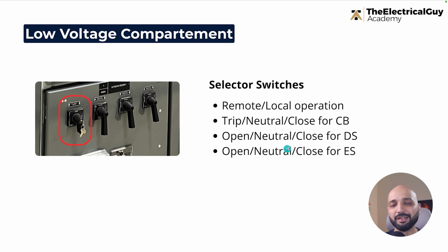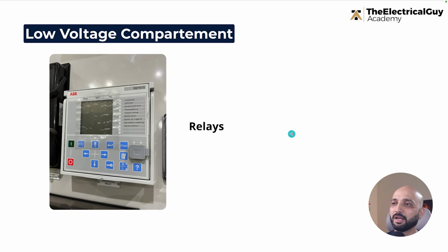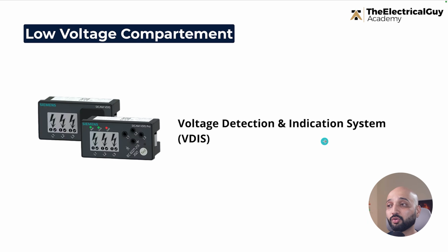And then of course, definitely relays. You will find a lot of relays placed there depending on the application. Different types of relays, electronic relays, and everything will be there. For example, you can see one relay here. It provides multiple functions. We have overcurrent, earth fault, sensitive earth fault, phase unbalance, thermal overload, breaker failure, condition monitoring, trip circuit failure. It's a long list, right? So you can have multiple relays also placed inside this. So those are relays.